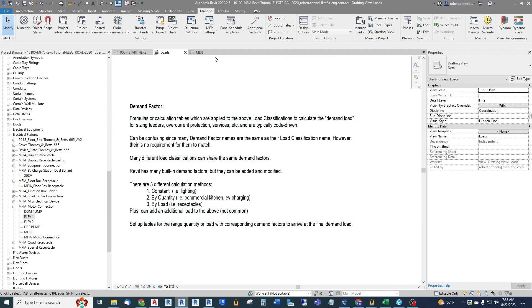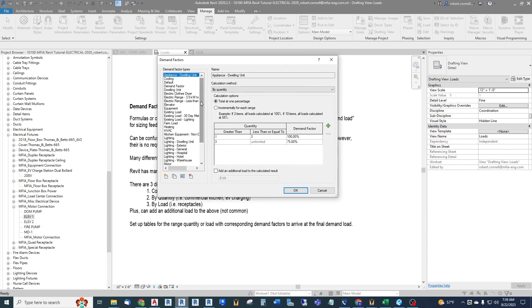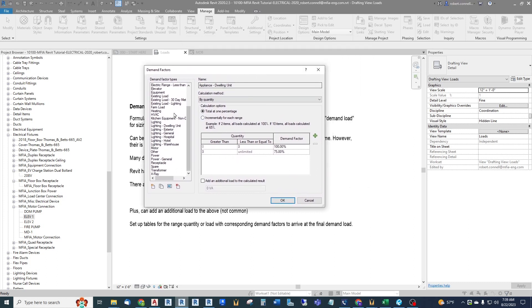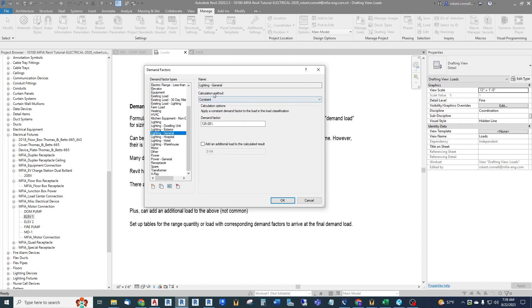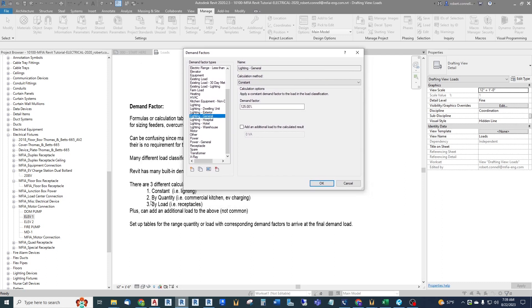Under MEP Settings, Demand Factors, the list looks similar to the load classification list — which is confusing — but this contains the actual formulas. For example, looking at Lighting General, the calculation method is Constant. It applies a constant demand factor of 125% of the connected load to arrive at the demand load — continuous load. There's also an option to add additional load, which we don't typically use.